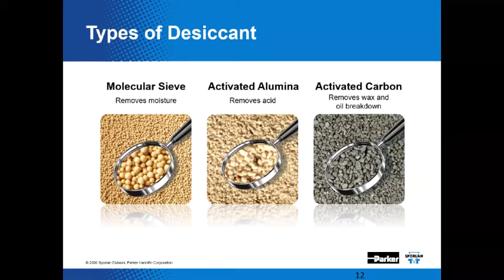Types of desiccant — we've got to eliminate these problems, so appropriate materials are deployed into catch-alls. Molecular sieve is very effective at removing moisture from the system. Activated alumina is very effective at targeting acid because of the size of the molecule. Activated carbon is able to remove oil breakdown material and waxy substances. Oil breakdown material means the oil has been deformed or damaged by some other event or contaminant so that it no longer provides adequate lubricity to moving components.